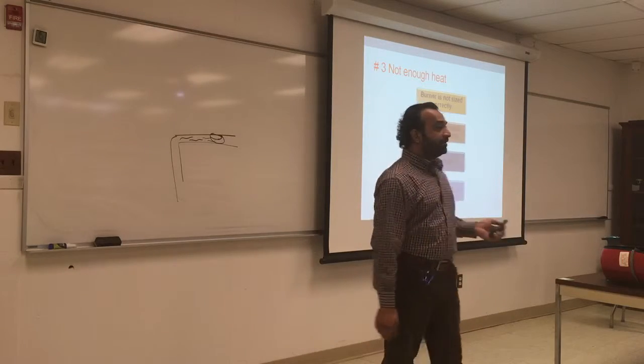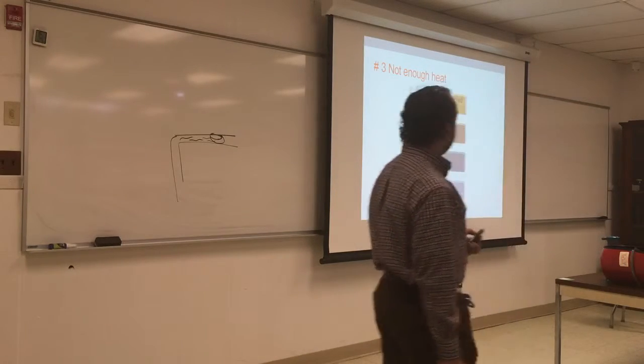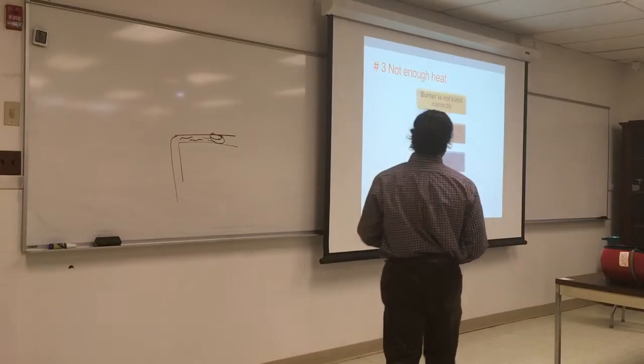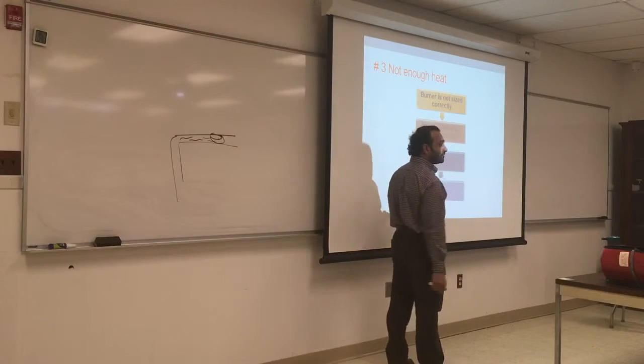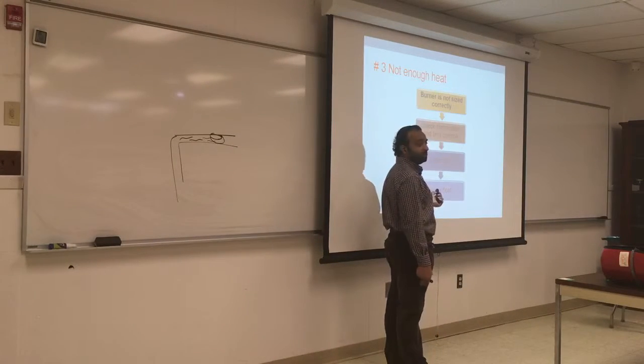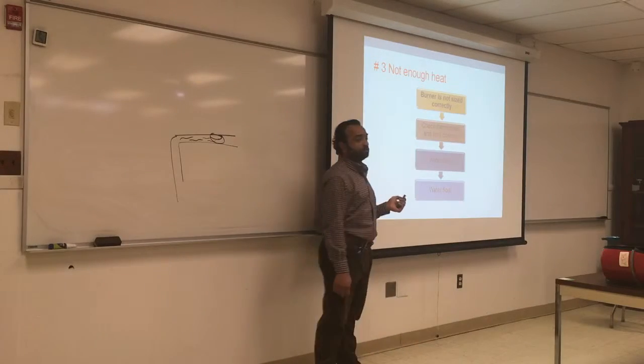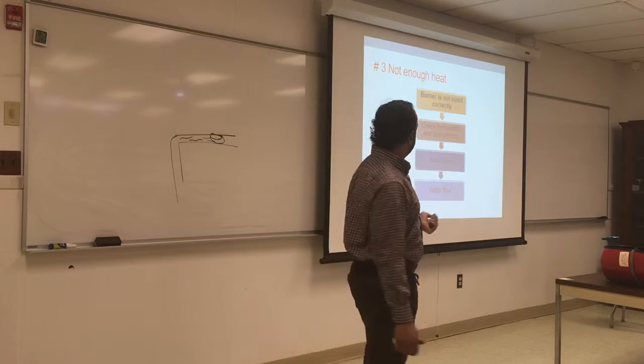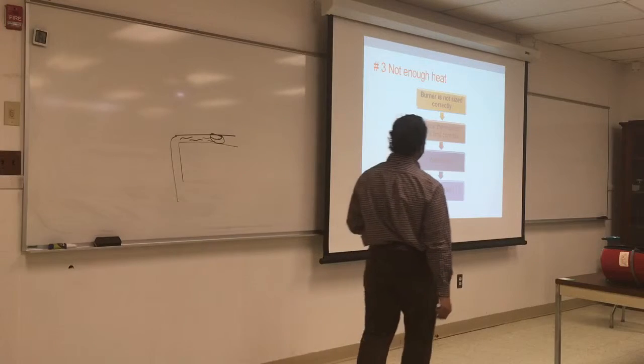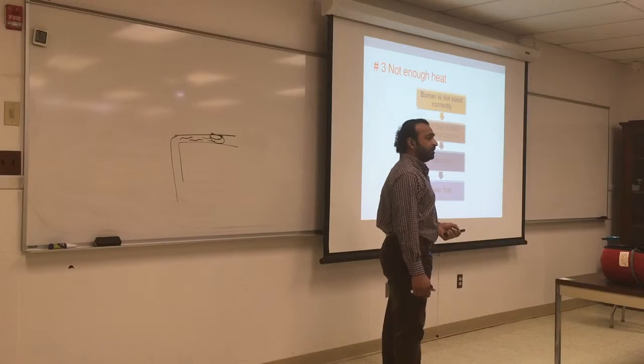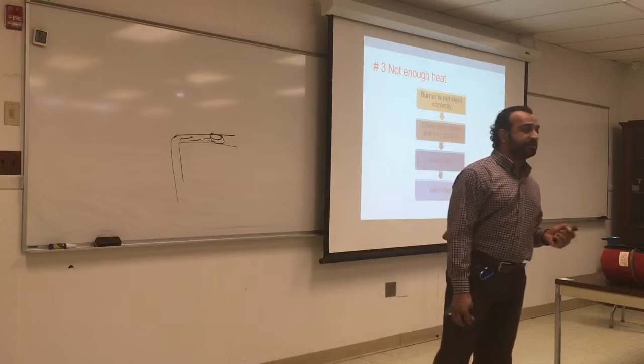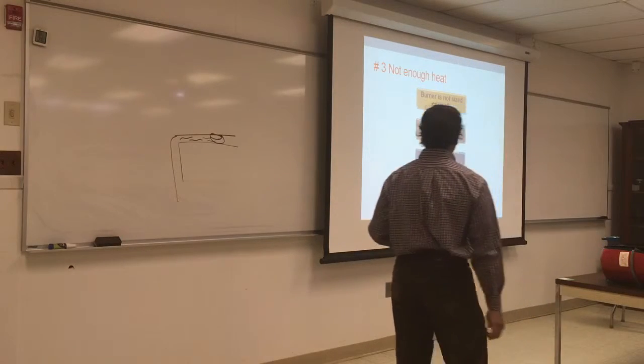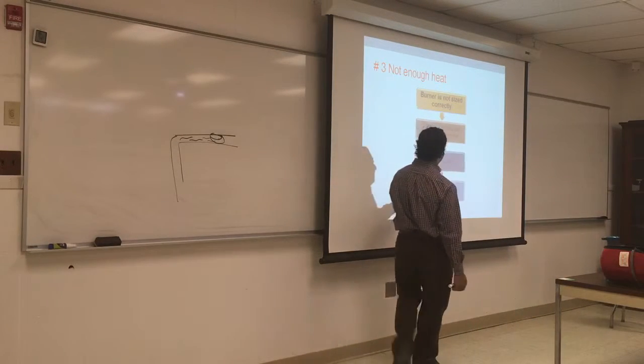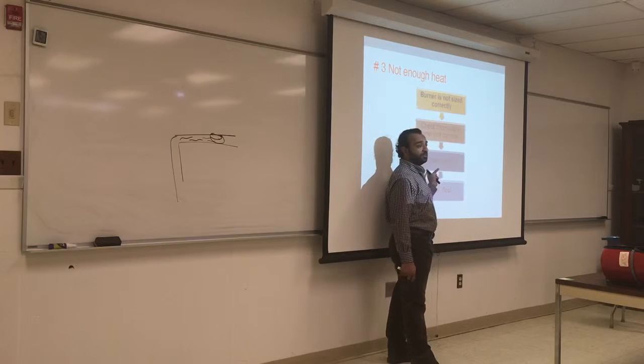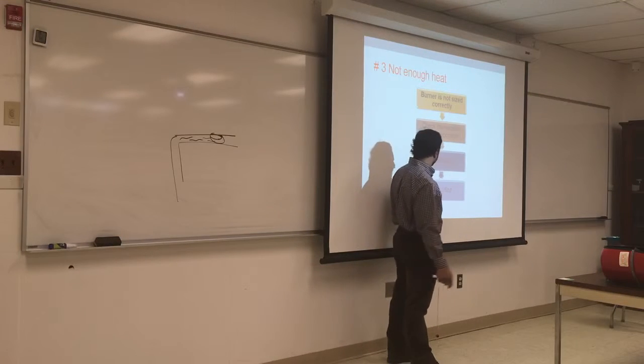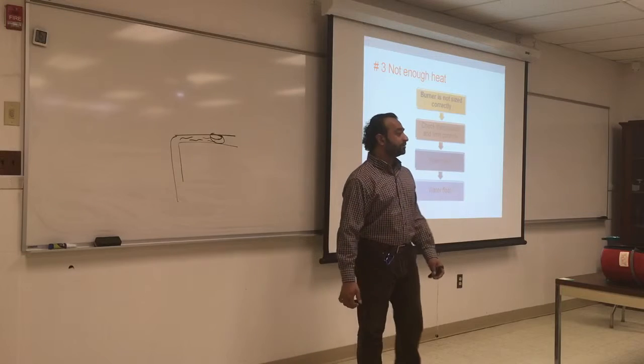If you do not have enough heat, it could be the burner is not sized correctly. So you've got to check, is this problem new or old? What caused it? Check the thermostat and control limit. Make sure the thermostat is reading the right temperature. Check the water level. Again, we said if there's low water in the hydronic system, you might not get enough hot water circulating. Check the water float.